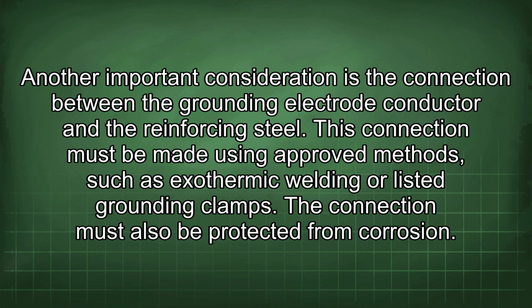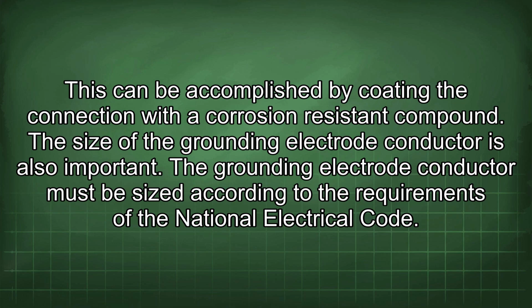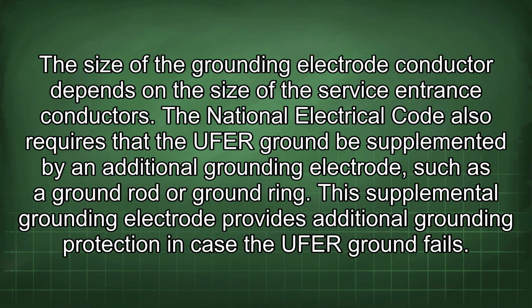Another important consideration is the connection between the grounding electrode conductor and the reinforcing steel. This connection must be made using approved methods, such as exothermic welding or listed grounding clamps. The connection must also be protected from corrosion. This can be accomplished by coating the connection with a corrosion-resistant compound. The size of the grounding electrode conductor is also important. The grounding electrode conductor must be sized according to the requirements of the National Electrical Code. The size of the grounding electrode conductor depends on the size of the service entrance conductors.